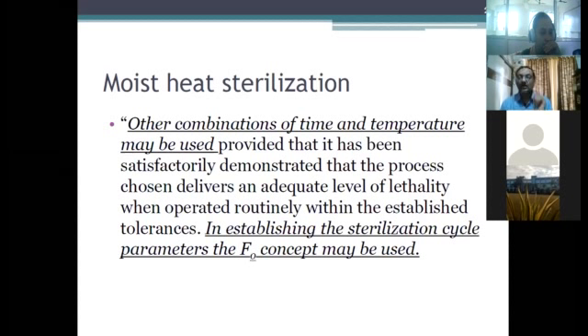All these are not amenable to 15 psi, 121 degrees centigrade. Why? Because that plastic becomes soft at that temperature. So you are not able to use 121 degrees centigrade, 15 psi, 15 minutes. You are therefore compelled to use a lower temperature, because otherwise the bottles become soft. So you are deviating from the standard conditions. In such cases, say you are using 110 degrees centigrade for autoclaving. It is not 115 or 121.